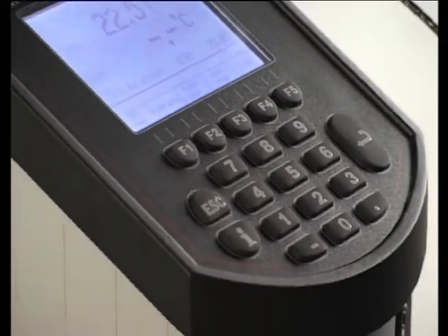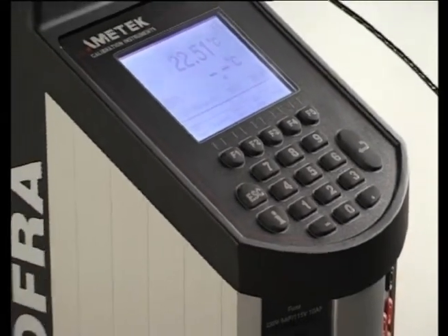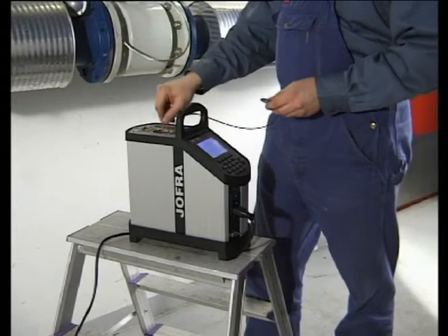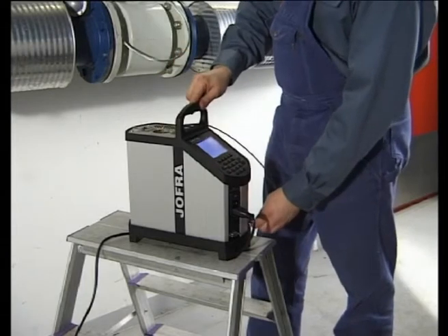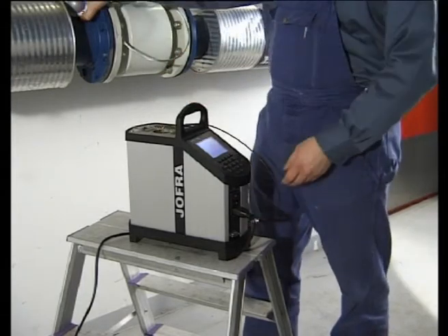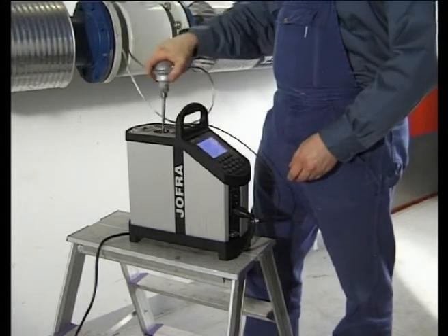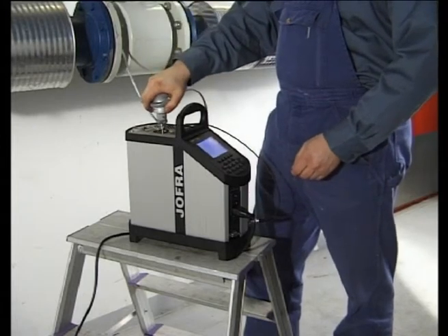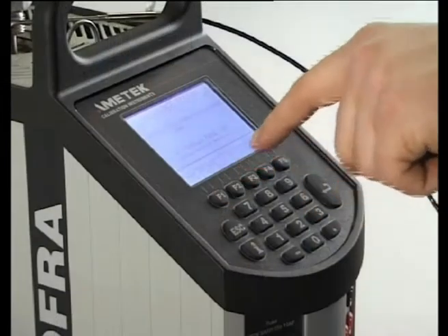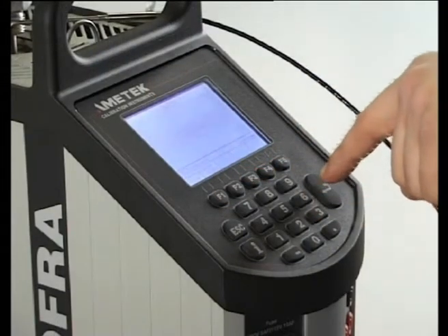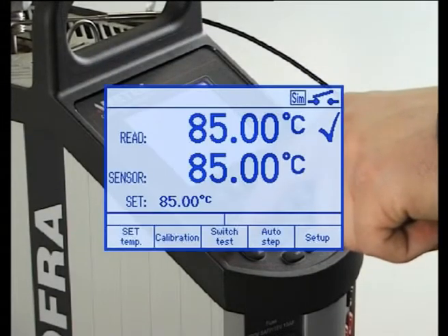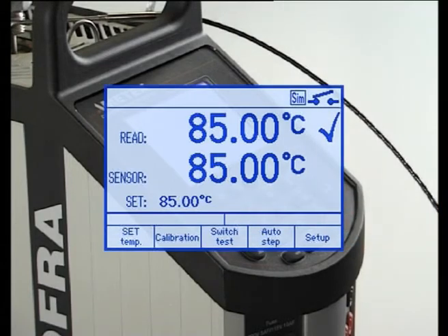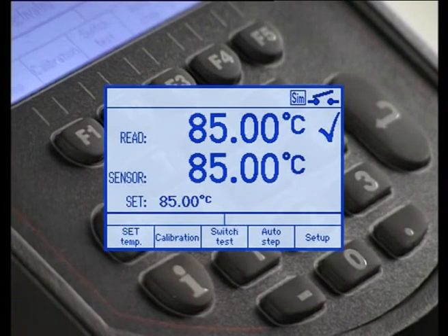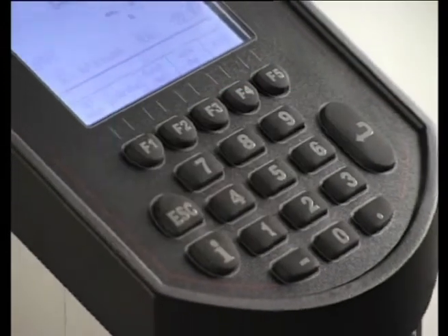For that purpose, we have developed a short-angled reference sensor. You can quickly mount it in the well, and there is still room for test sensors, even for those with a transmitter head, top connector, or similar arrangement. You decide whether you wish to read the built-in reference sensor or the more accurate external reference on the calibrator's large display. The external and internal reference sensors are still independent of each other.